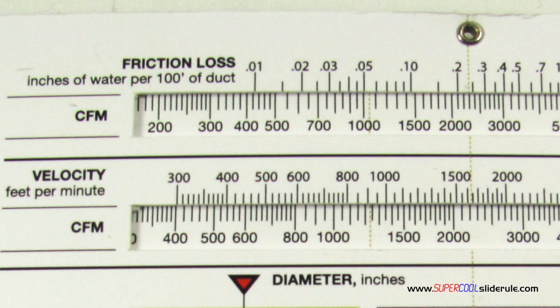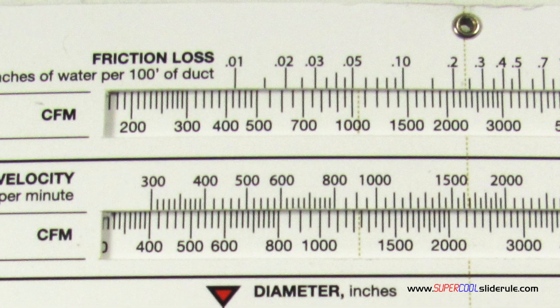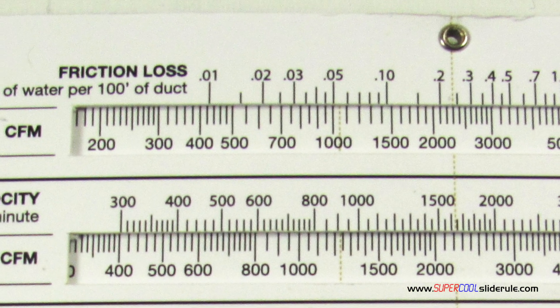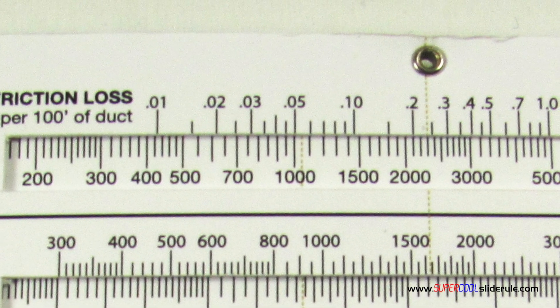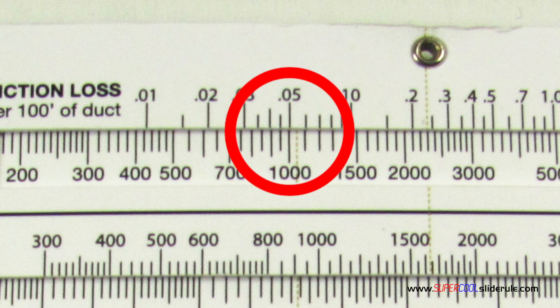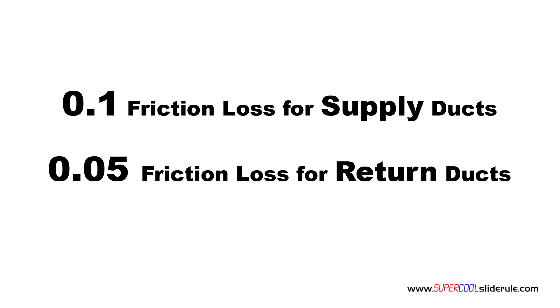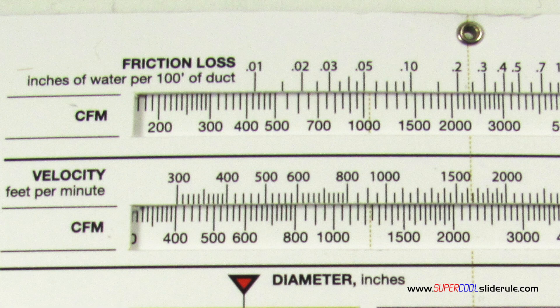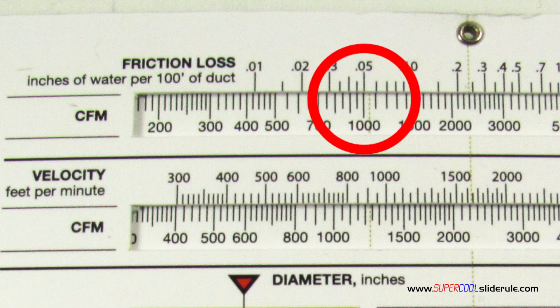Next, we size the return air duct. The return air duct is sized by indexing the total required CFM directly under .05. To restate, we use .1 for all the supply ducts and .05 for all the return ducts. So our total CFM of the system was 1000. We index it under the .05, looks just like this.